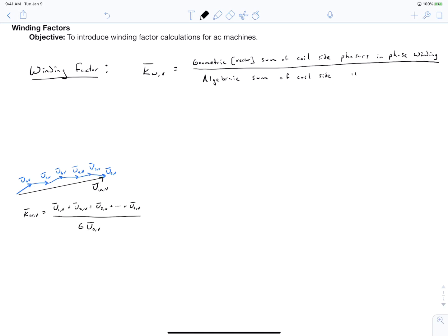The winding factor is the phasor sum of each coil side's phasor divided by our number of coil sides times the phasor of a coil side at slot alpha equals zero. We can write this as the vector sum of coil side phasors divided by the algebraic sum, summing over index i from 1 to 2n, where n is the number of coils in a phase and 2n accounts for two coil sides per coil.